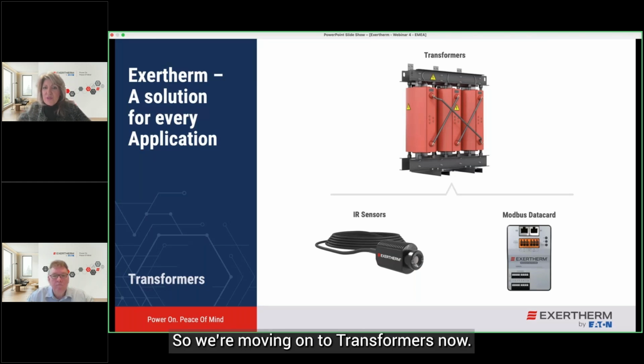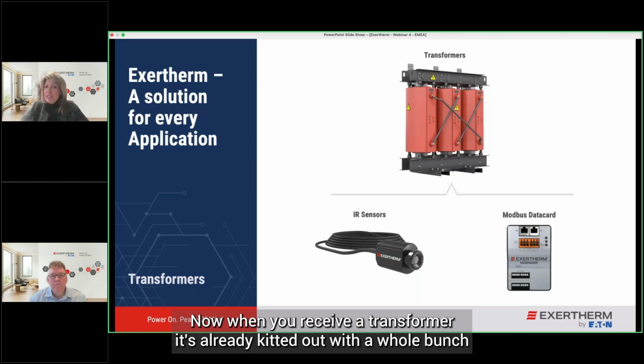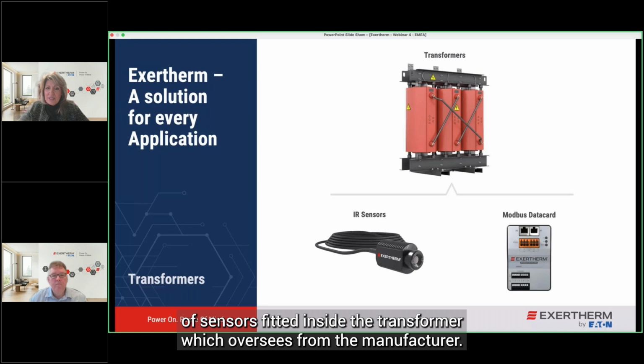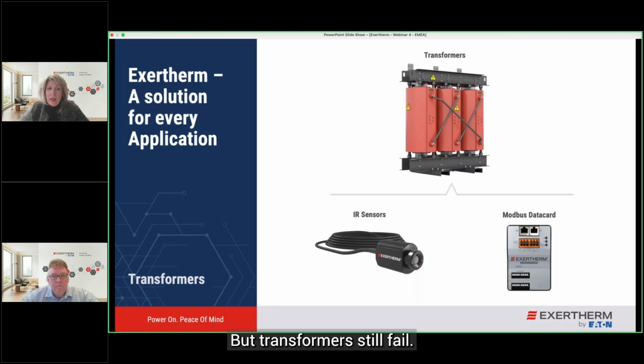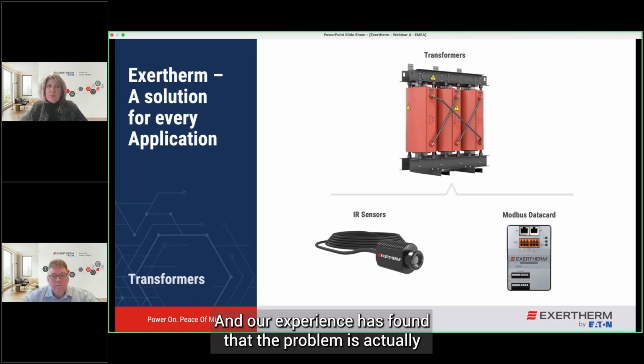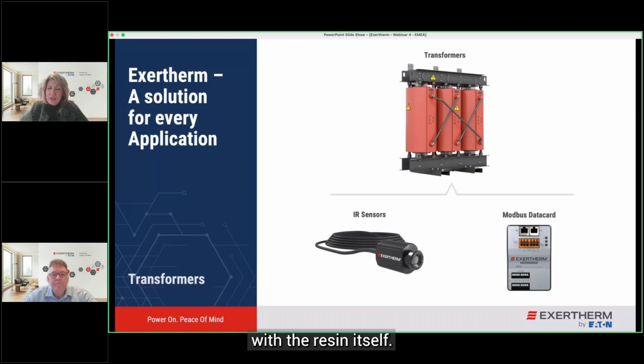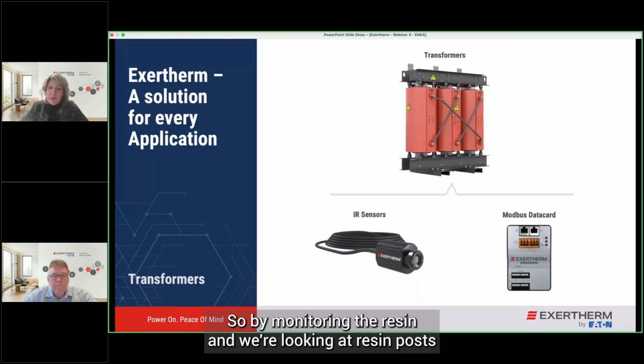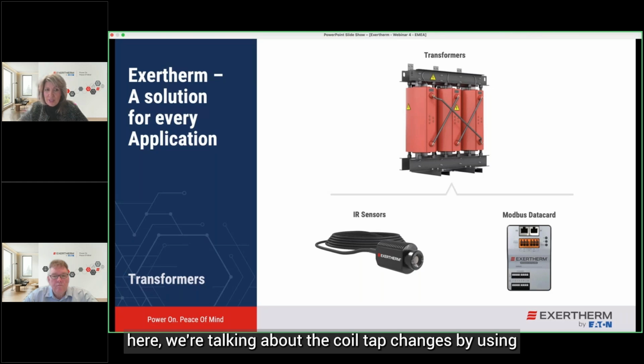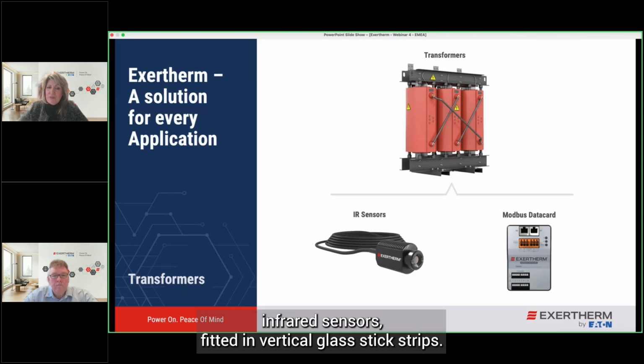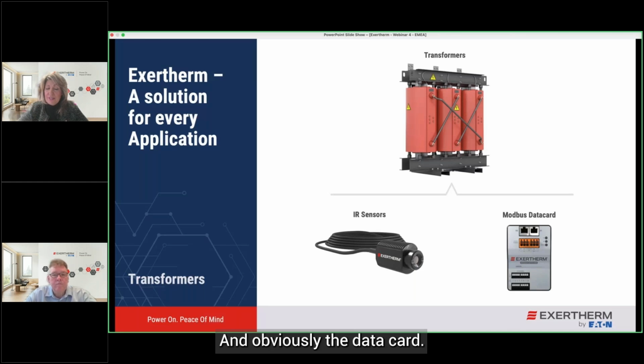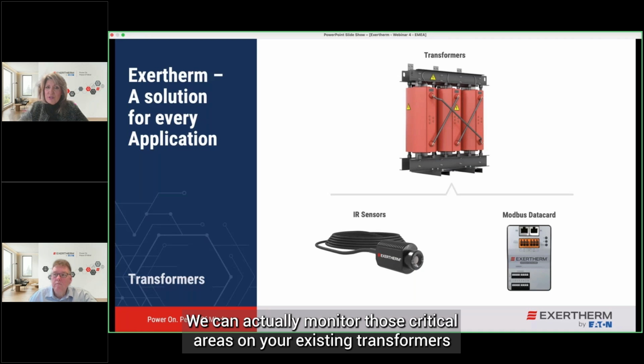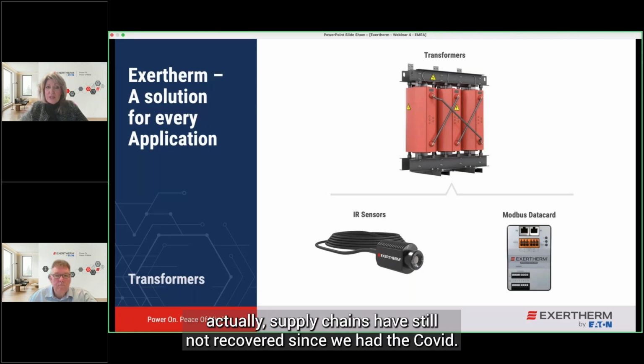So we're moving on to transformers now, and specifically here we're looking at dry type resin cast transformers. When you receive a transformer, it's already kitted out with a whole bunch of sensors fitted inside, from the manufacturer. But transformers still fail, and our experience has found that the problem is actually with the resin itself. So by monitoring the resin, and we're looking at resin posts here, we're talking about the coil tap changes, using infrared sensors fitted in vertical plastic strips and the data card, we can monitor those critical areas on your existing transformers.